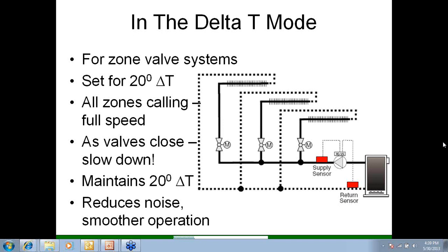Yeah, it's like I had said. I think that if you think about it in terms of this goes between your boiler and whatever was starting your boiler. Doesn't matter what was starting your boiler. Something was telling that boiler to turn on. And that wire, let's say there's a wire going to the boiler. It's coming from somewhere. We take it off the boiler, we put it on the fuel miser, and then we run a wire from the end switch on the fuel miser over to the boiler. It's a go-between. That's a really good way to put it, John. A go-between. There you go. Yeah, it's kind of like a mediator, so to speak.